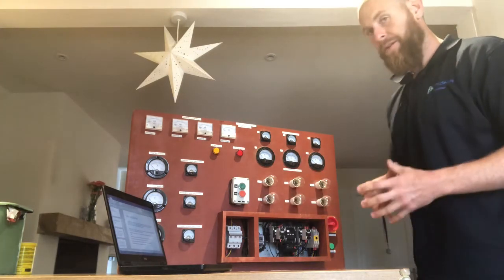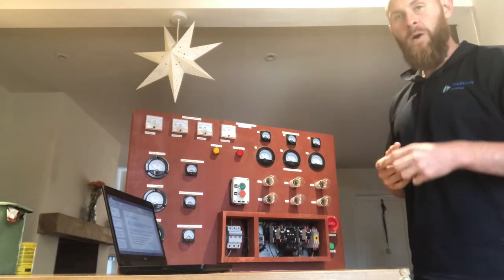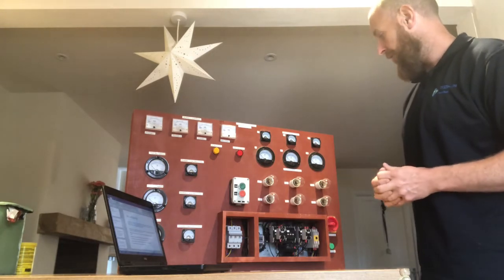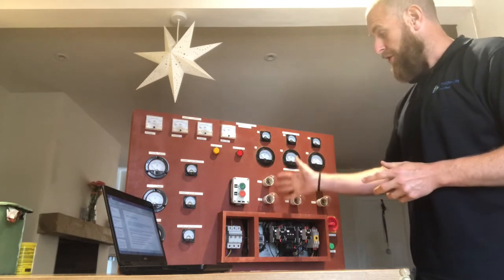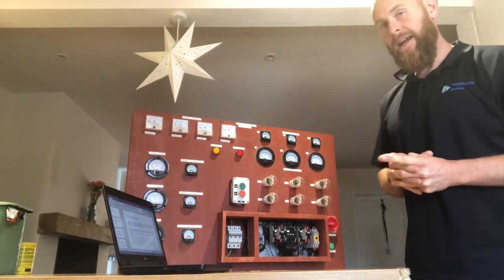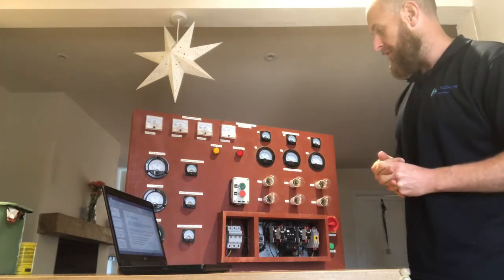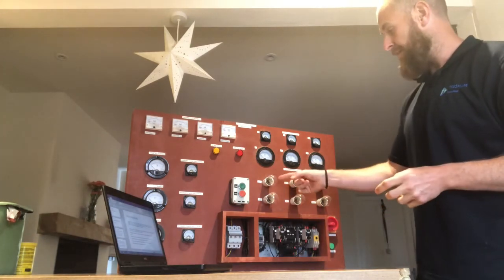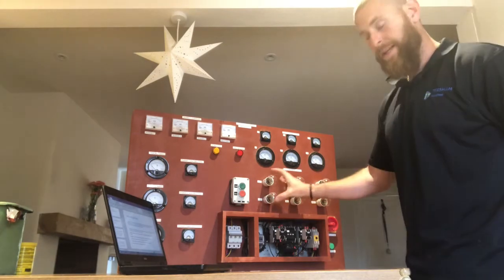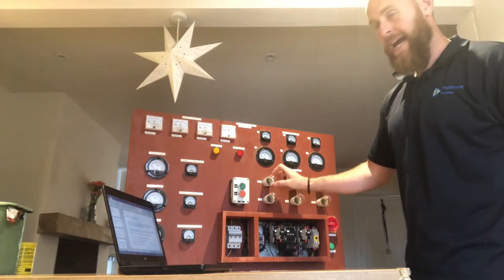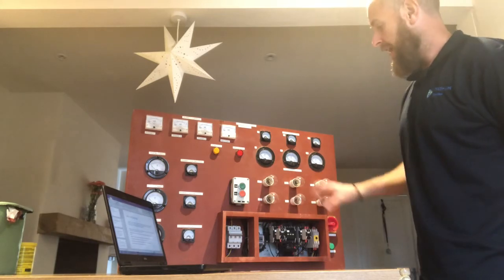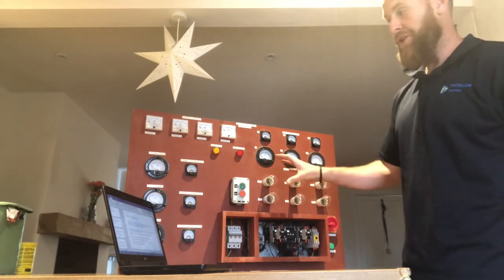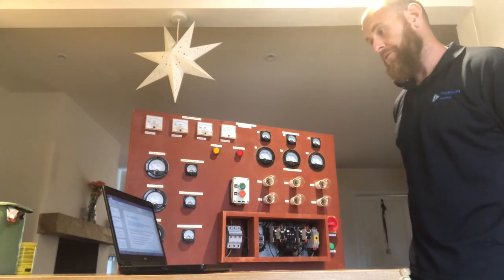We've got one pair, two pair, and three pair, and each pair of lamps is connected in series and represents the actual coil of a motor - that's the U coil, the V coil, and the W coil. On a three-phase motor the actual coils or the windings are labeled U, V, and W. When this is first started up these coils are connected in the star arrangement, that means that they are only going to be operating at 230 volts. When you apply 230 volts over two lamps in series each lamp is only going to work at a quarter of their power. When it moves over to delta and 400 volts is applied across these, they're going to have much higher voltage across them and therefore they're going to shine brighter.